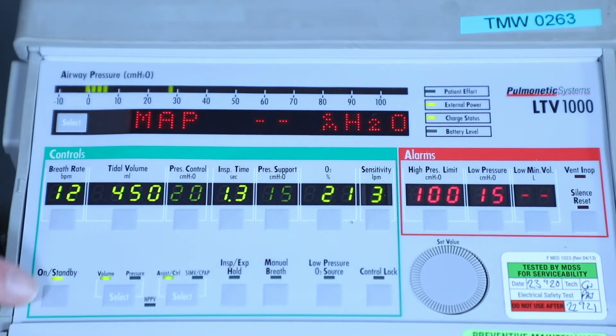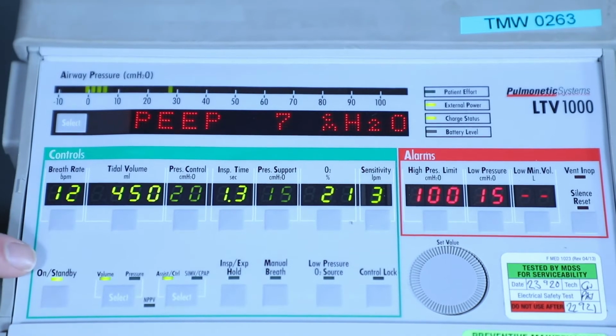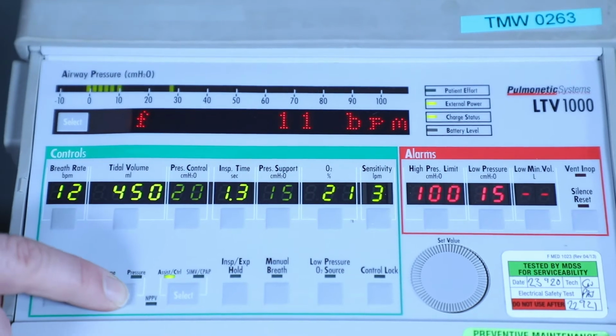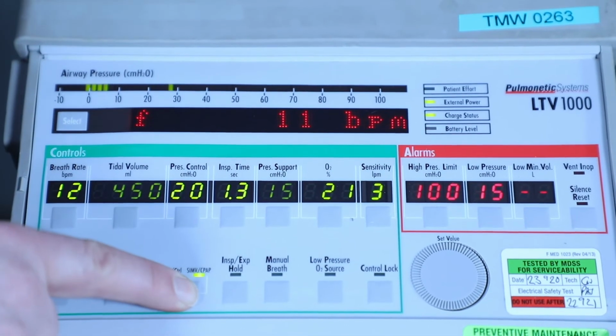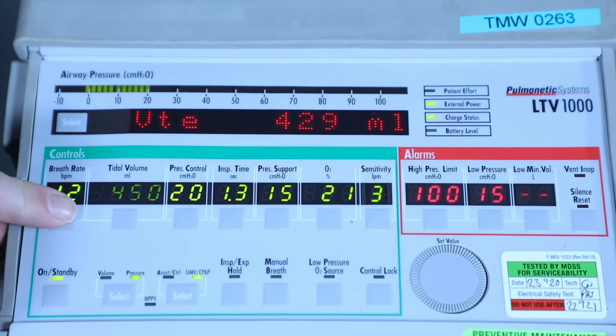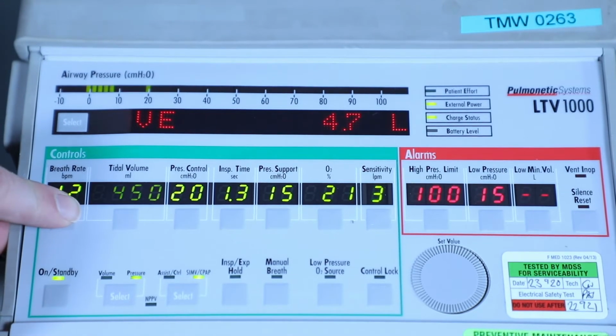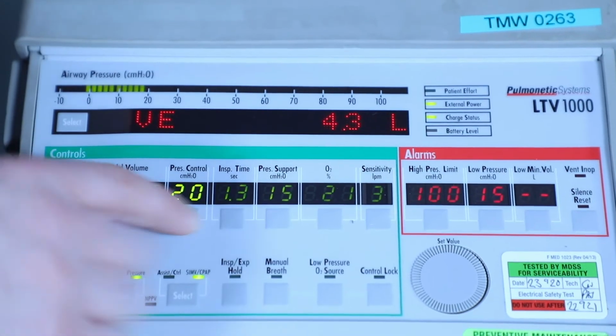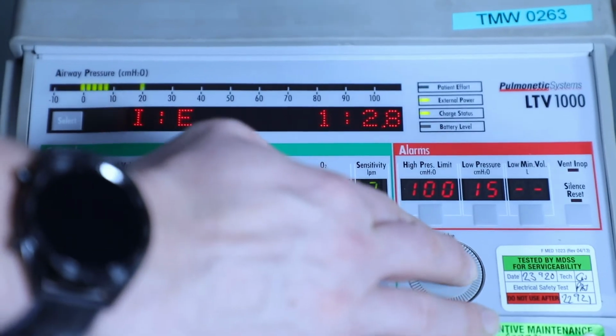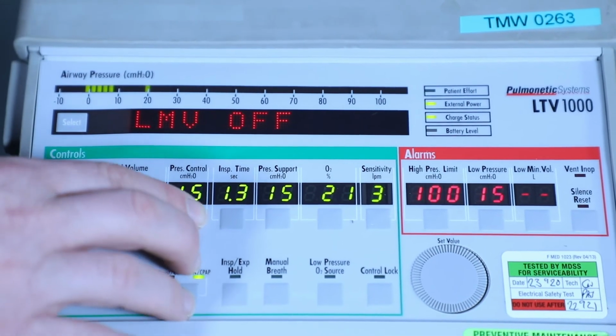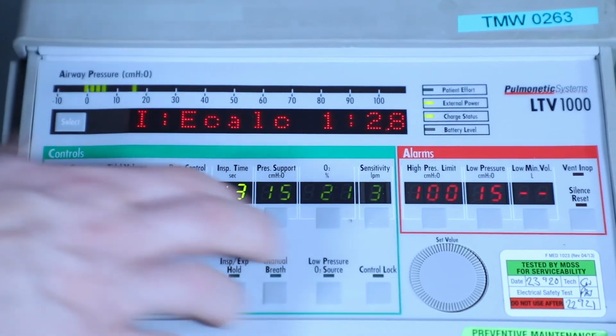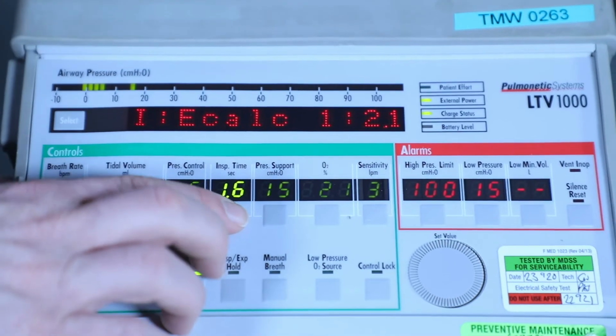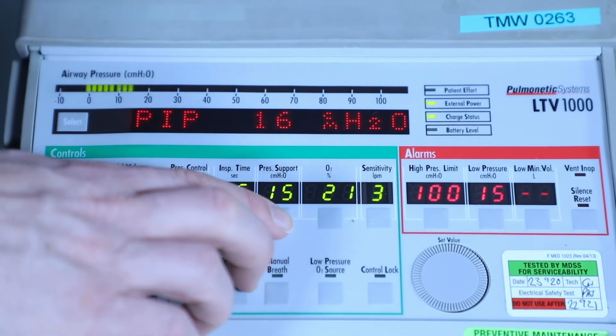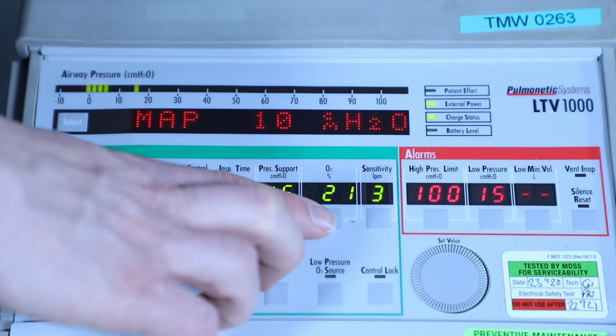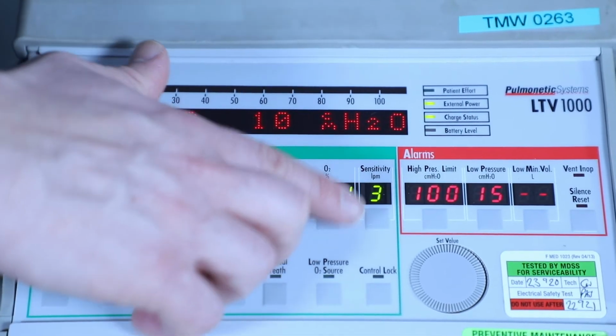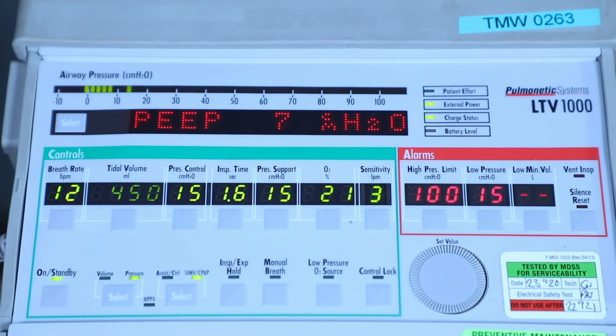So from here we just want to select some nominal values. We put the system into pressure SIMV, respiratory rate of 12, pressure control of 15, inspiratory time of 1.6, pressure support of 15, leave the oxygen at 21%, and the sensitivity to 3 liters per minute.